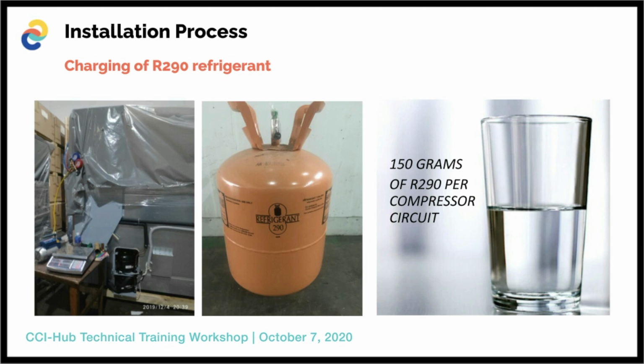The operating pressure follows standards: 15 to 25 psi on the low pressure side, depending on the ambient temperature, especially in the Philippines, where we are in a tropical country. The high pressure side of the system is 220 to 240 psi, which is almost the same as refrigerant R22, if you are familiar with it.